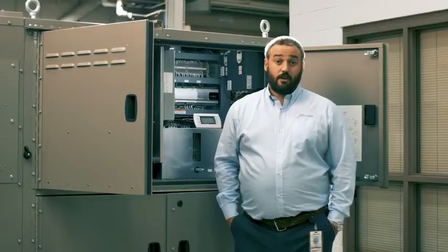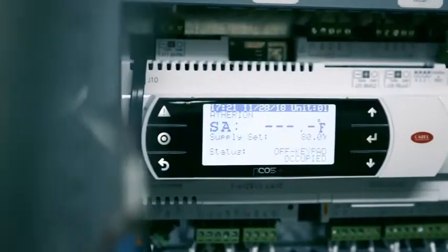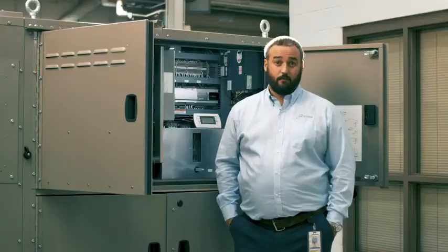So when the unit's running, you actually get real-time data from those 200 variables, which means you can see the system's health and performance while it's operating. When looking at the BMS variables, you can go as far as to look at the electronic expansion valves and the subcool and the superheat. And by doing that, you can troubleshoot the unit, which means if you go in and look at your values, you can work out whether the unit is low on refrigerant due to the fact that the superheat is very high and the valve is fully open. And you can also look at whether the subcool is where you expect it to be. And this can point you towards whether the unit is short of refrigerant or actually has an issue. And that's all done through the PC without even going up to the unit.